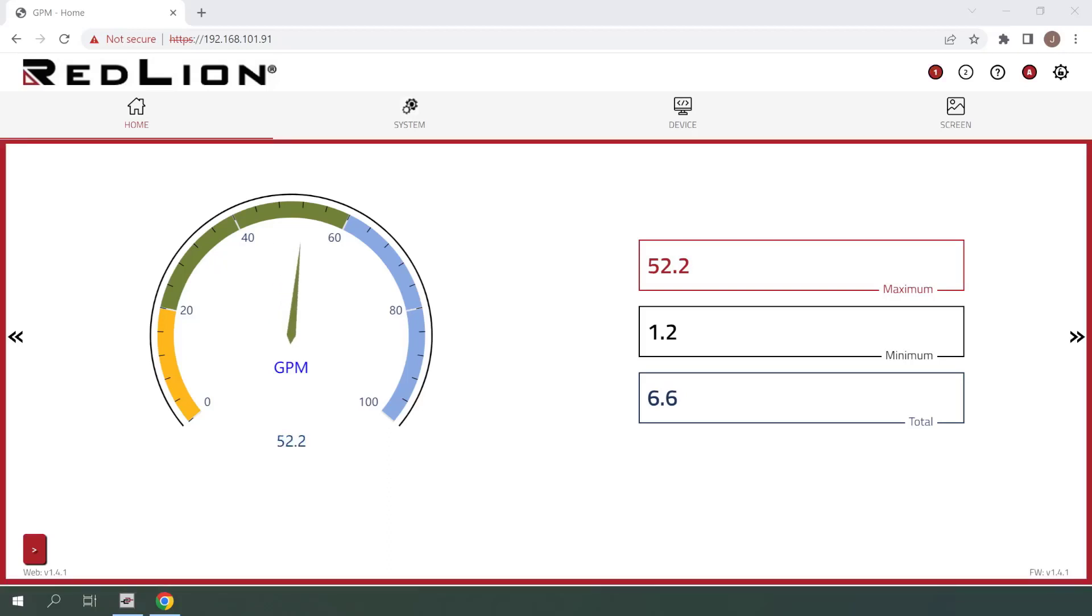As you can see from the red enunciator border, the alarm has triggered and since it is a latching alarm, it will stay on until we clear it, even when the flow returns to normal. I'll bring the flow back down below 50 GPM and you'll see that the latching alarm will still be triggered because we need a way to reset it.